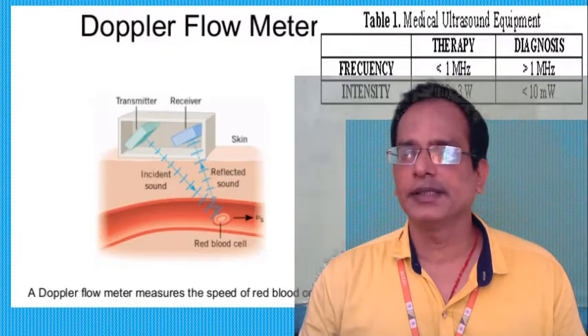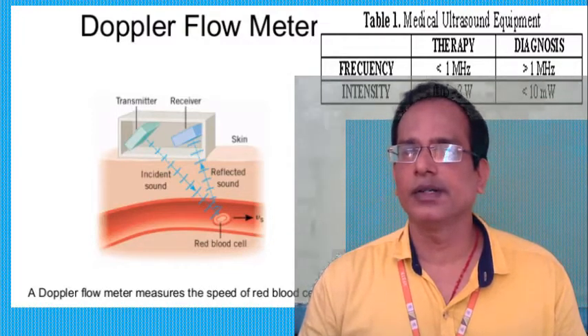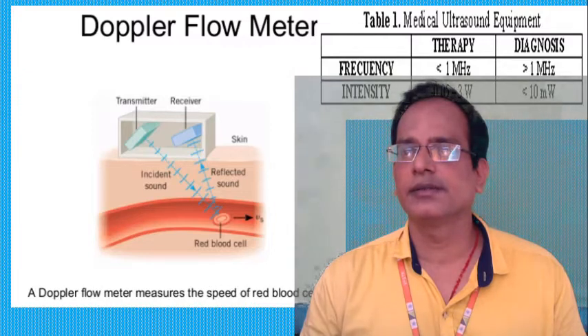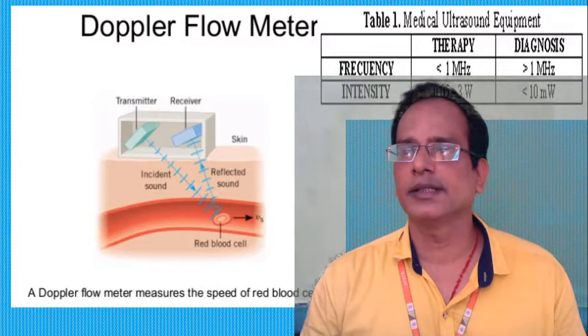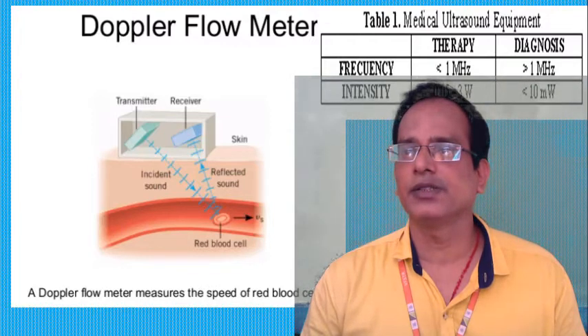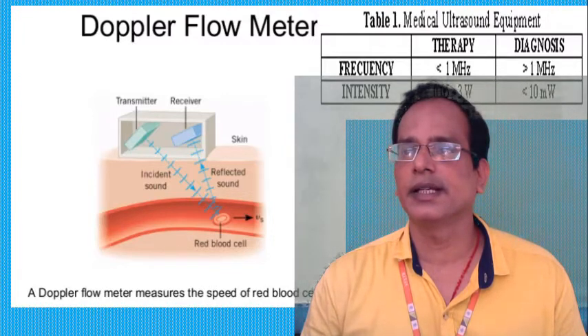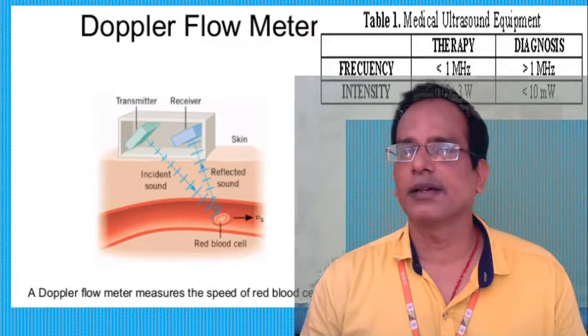Another key application is the Doppler flow meter. Doppler flow meter medical ultrasonic equipment is used for measuring blood flow information. Frequencies less than one megahertz are used for therapy purposes, and greater than one megahertz for diagnostic purposes. Intensity level for therapy is 0.05 to 3 watts; for diagnosis it is less than 10 milliwatts. A transducer and receiver in a Doppler flow meter are used to find the velocity of blood flow.